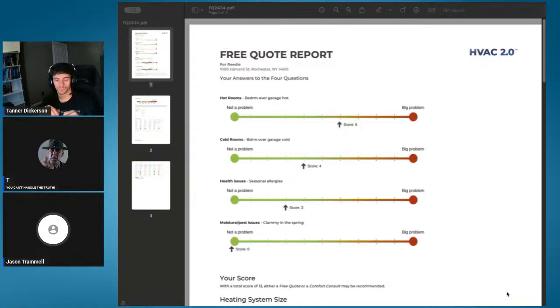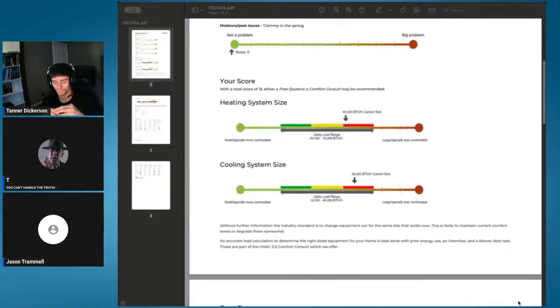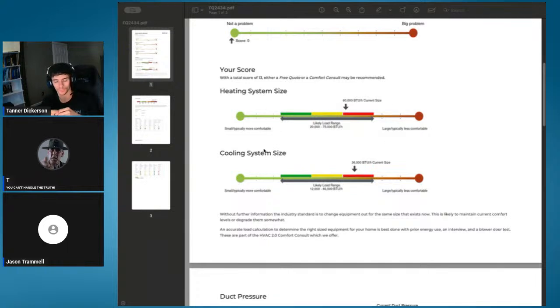But in the homeowner's eyes, it's: they sold me too small of equipment, rip it out and replace it on the company's dime because they didn't go through your process. Most people don't use free quote counselors. Most people in that situation are oversizing the equipment and burning up blower motors and not getting the capacity they were sold, so going bigger in that case makes the problem worse. Yes, and if they go from oversized to grossly oversized, that again is a sales process problem, solved with likely load range.